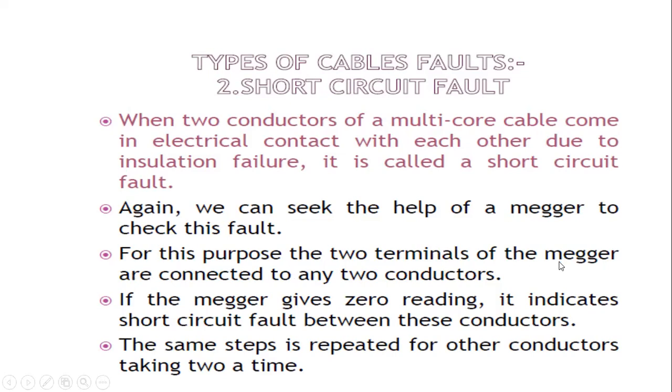For this purpose, the two terminals of the Megger are connected to any two conductors. If the Megger gives a zero reading, it indicates a short circuit fault. If the Megger gives the zero reading, then we identify that a short circuit fault is obtained in the line, between these conductors.